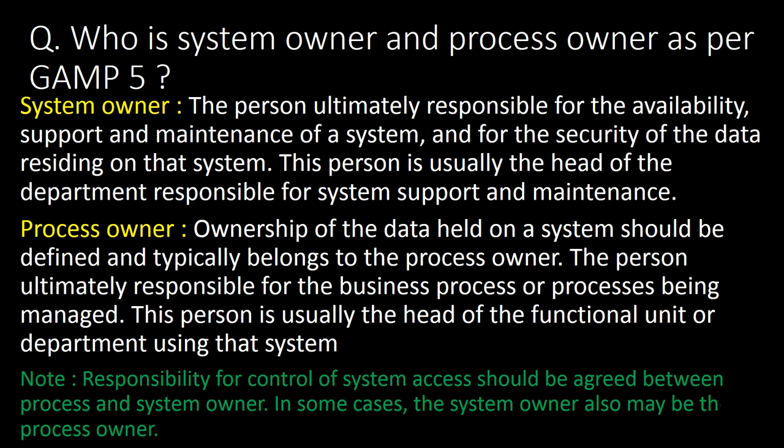Who is the system owner and process owner as per GAMP-5? As per GAMP-5, the system owner is the person ultimately responsible for the availability, support, and maintenance of a system and for the security of data residing on that system. This person is usually the head of the department responsible for system support and maintenance. The process owner is the person ultimately responsible for the business process or processes being managed. This person is usually the head of the functional unit or department using that system. Responsibility for control of system access should be agreed between the process owner and system owner. In some cases, the system owner may also be the process owner.